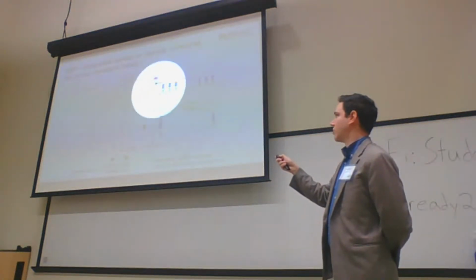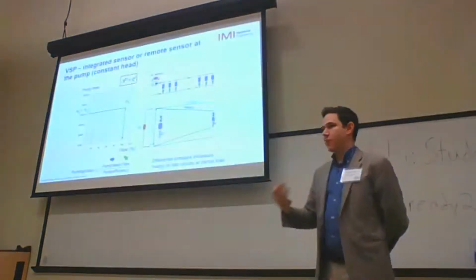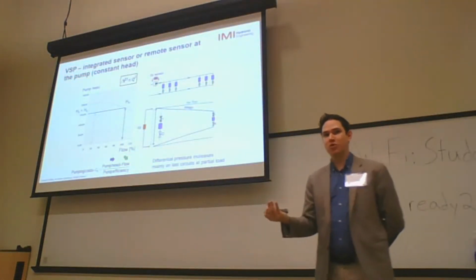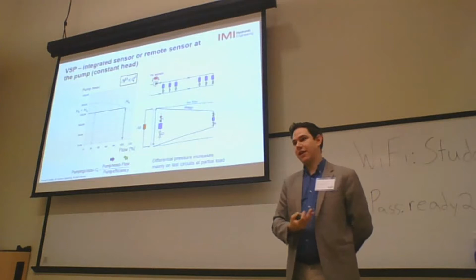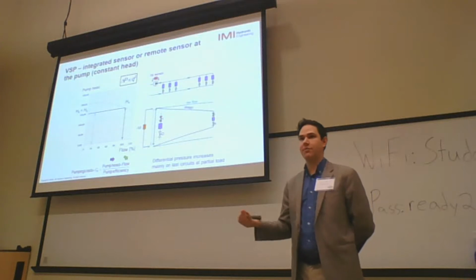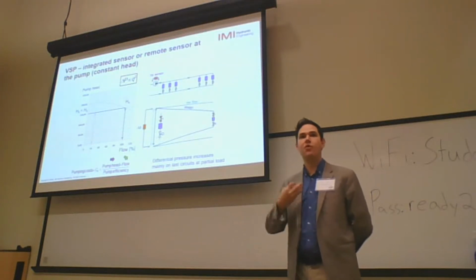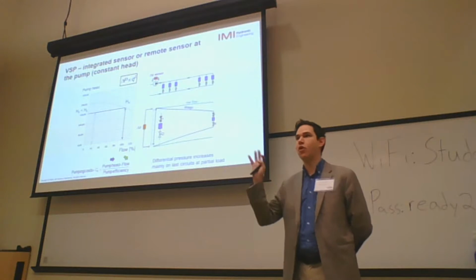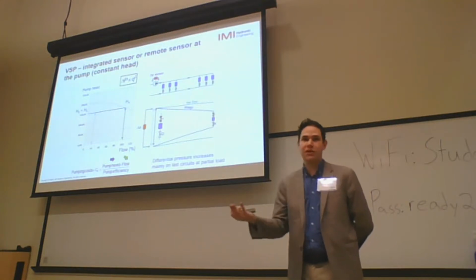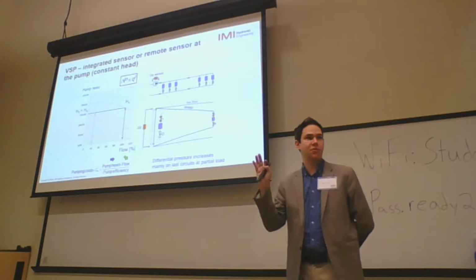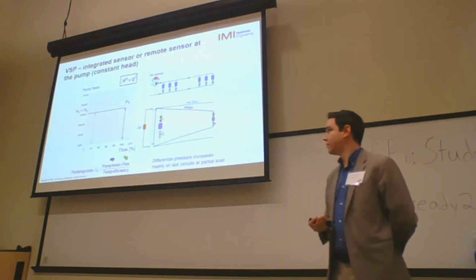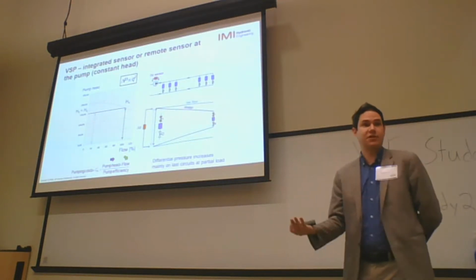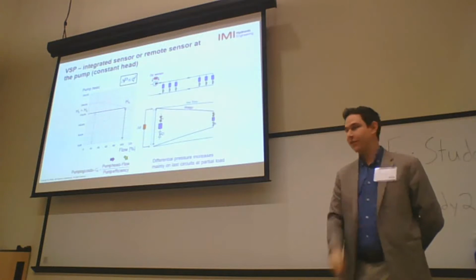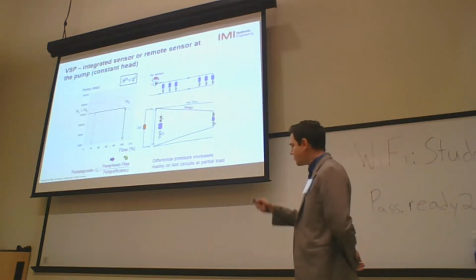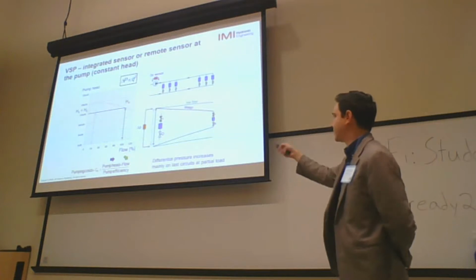If you place the DP sensor right there, closer to the pump, you're basically getting your pump working at almost the highest speed the whole time, with no energy savings, but you're always guaranteeing that you have enough water for the whole system. So that is kind of a safe bet. Just place it close to the pump and that's it. But you have zero energy savings, so that's bad when you're thinking about energy consumption.